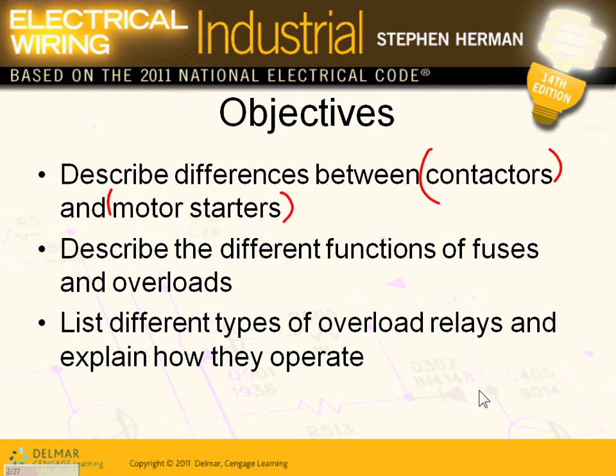You have a contactor that opens and closes. We were sizing it yesterday. What did we put — that little tiny thing that protects? Overload. Thank you. So if you add an overload to a contactor, you have just created a motor starter. That's a motor starter. A contactor just doesn't have an overload. You add an overload to it, you've created a motor starter. So they're very similar — different function if you use an overload.